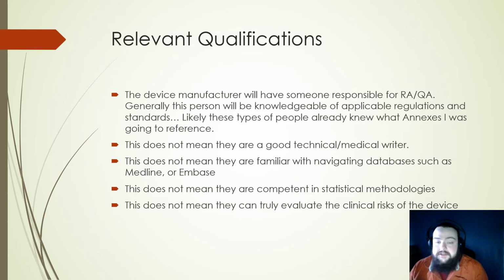But if you're having a consultant help with these, you should make sure that you are qualifying the supplier of these services, especially if you happen to also market your device in the United States, and perhaps maybe if you're maintaining ISO 13485. You can qualify your consulting services as suppliers. Even though it's not a physical product, they are supplying a service, and you need to make sure that the person you are getting the services from are competent and have the appropriate education and training.